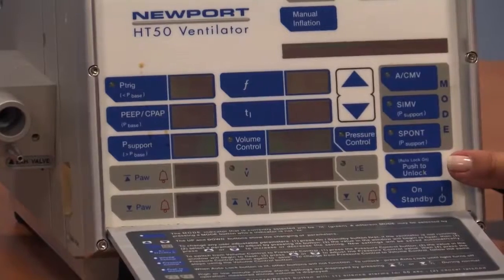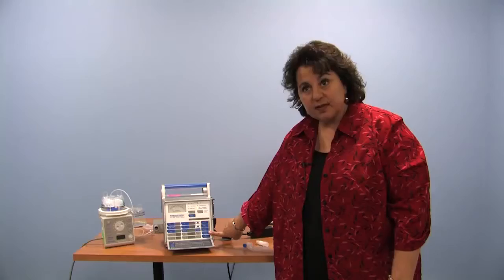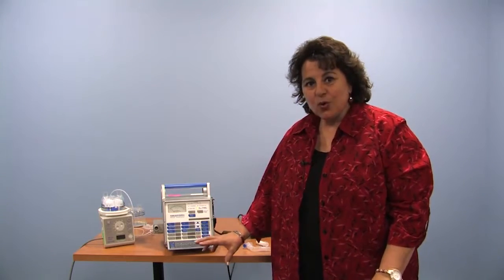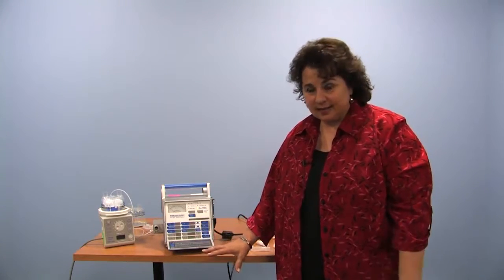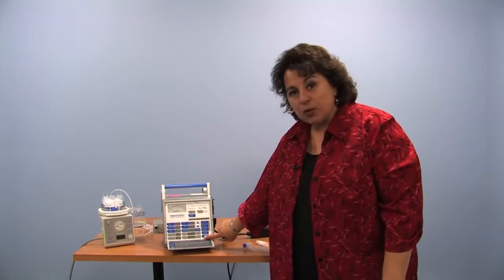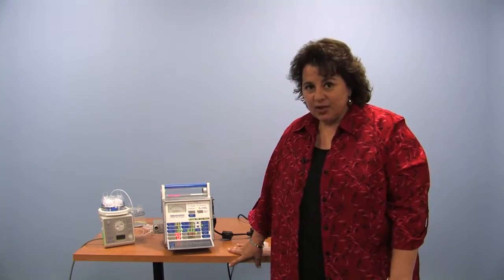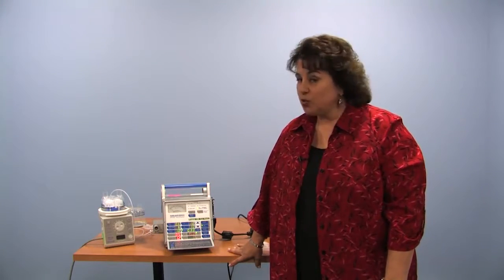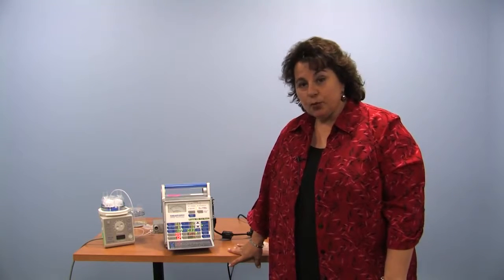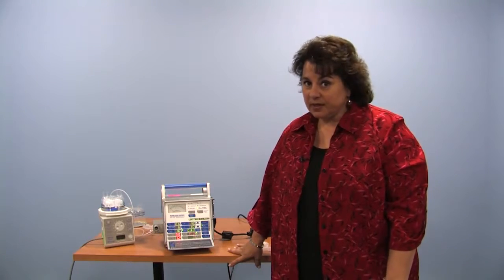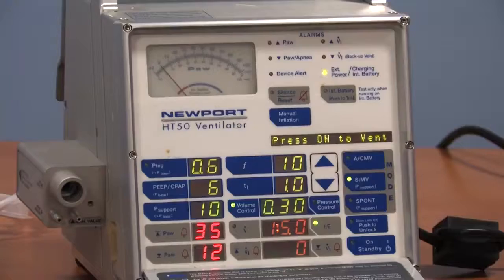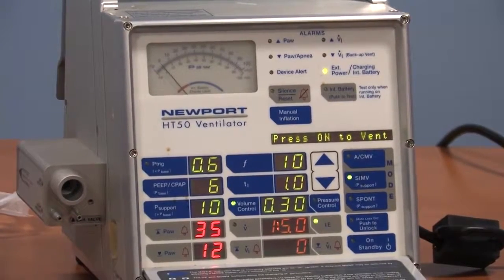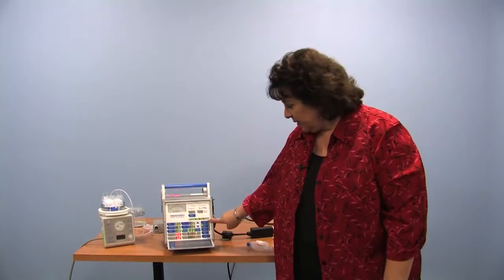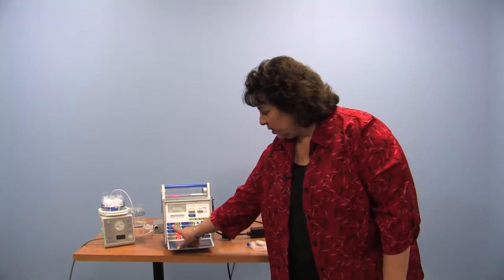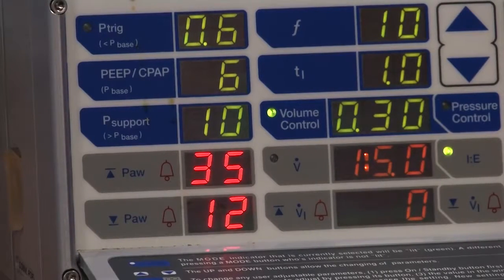There is a lock feature, so the machine can be locked so that other little fingers in the household, etc., cannot change the settings. I'm going to push the button once. This means we can view the settings, but it does not mean that your child is receiving ventilation. So do not put a person on the Newport HT50 until you've hit the button twice to start ventilation. What we see here is it does tell us that. Press on to vent.